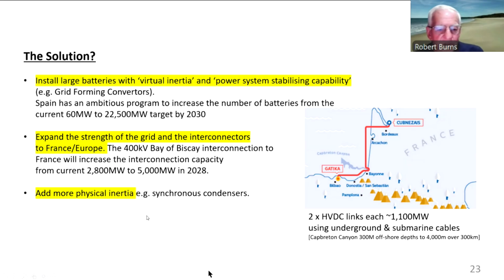The other thing you can do is add more physical inertia, and synchronous condensers is the answer there. They provide extra inertia. They can also control voltage, and they can help increase what's called system strength. And I just noticed tonight that there's a whole bunch more synchronous condensers to be installed in our system.